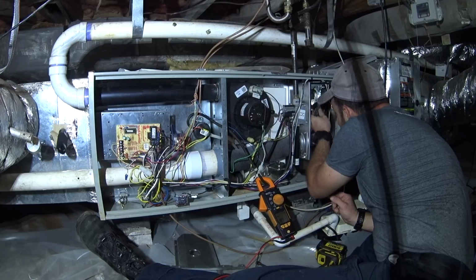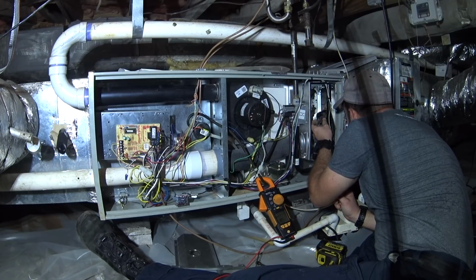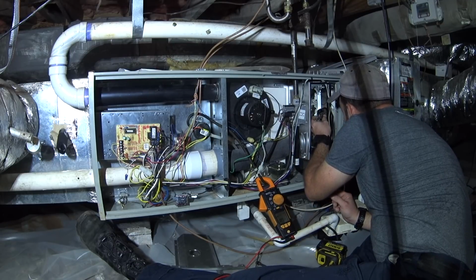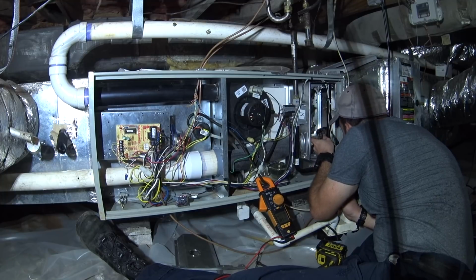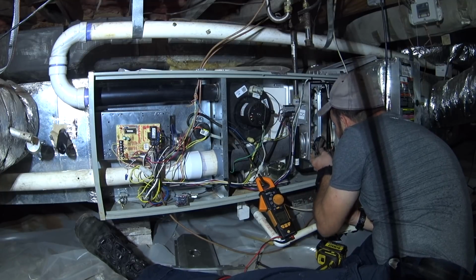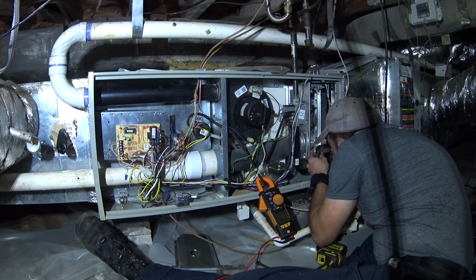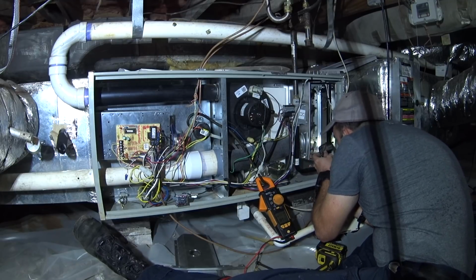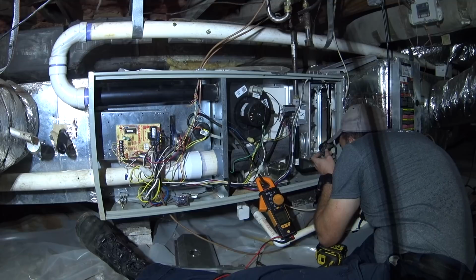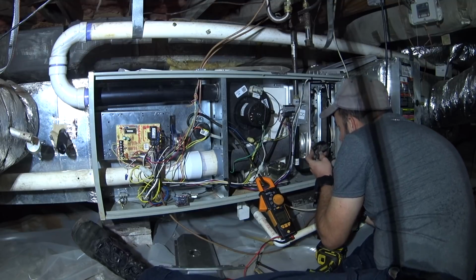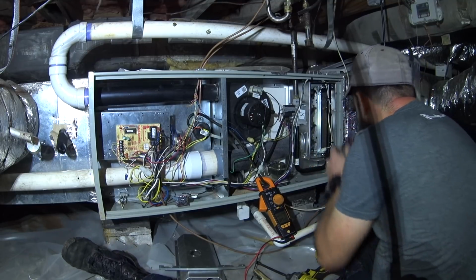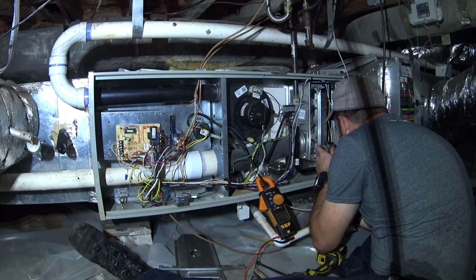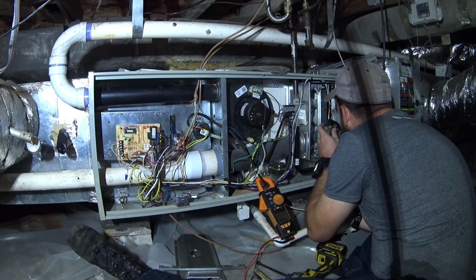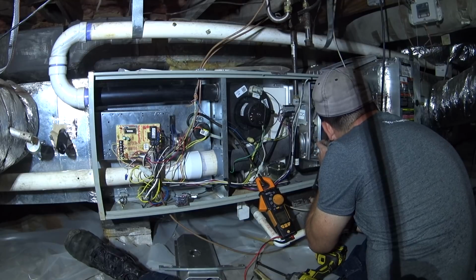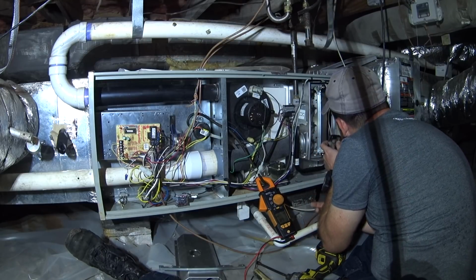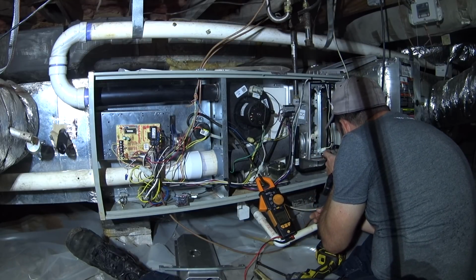When the inducer assembly was condemned several years ago, they actually claimed that there was a crack in the heat exchanger and that they needed to replace the system. And I don't feel like that is the case. After all of the testing that I did, I could not find any evidence of a crack in the heat exchanger, though I am kind of intrigued.